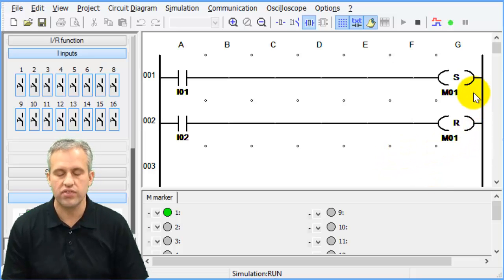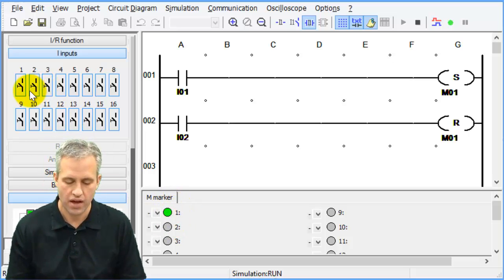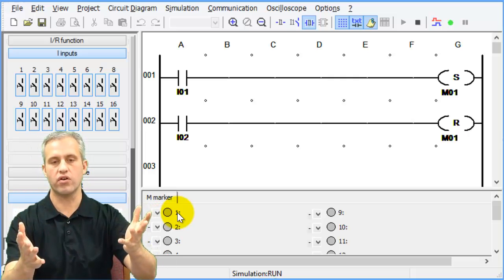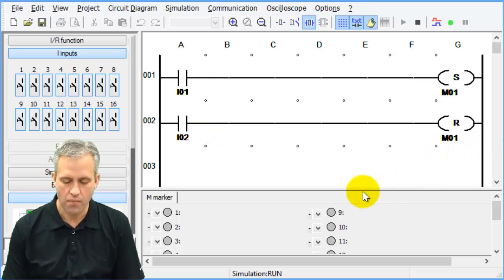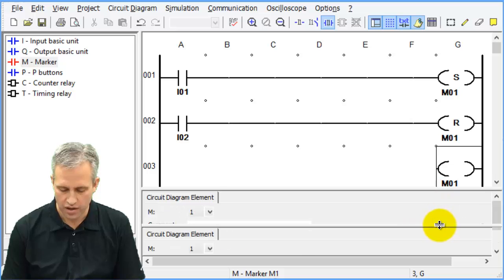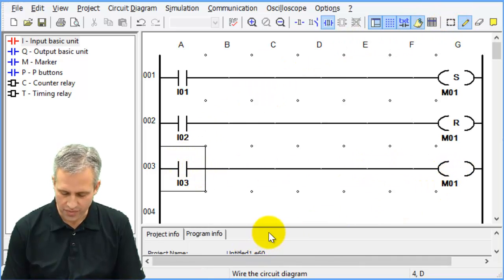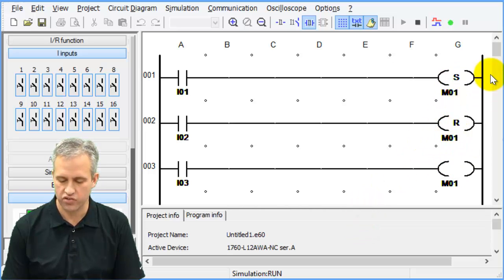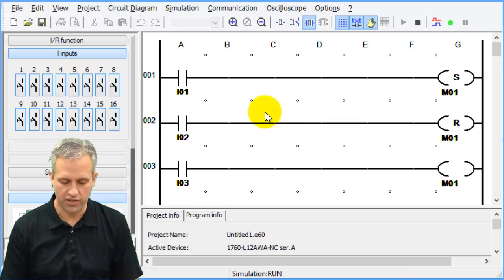In the simulation, I'll display the markers. If I hit I1, the line going to set goes high. The neat thing about set and reset is that as soon as I let go, you can see the marker actually stays set. If I hit I2, it resets the marker. So with set and reset, you can set whether something is on or off and then remove the stimulus — it stays set. Reset turns it off. One important note: you have to be really careful not to over-constrain something.